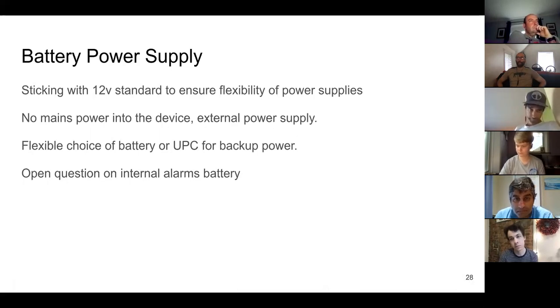We're not bringing mains power into the device - we'll use an external power supply rather than plugging AC into the wall, which goes toward standardization as well as safety. This gives people flexible choice, whether they use a large battery or UPS for backup power, or if the hospital is on backup power, that's another option. That's us falling into the TLA trap again - UPS stands for uninterruptible power supply.